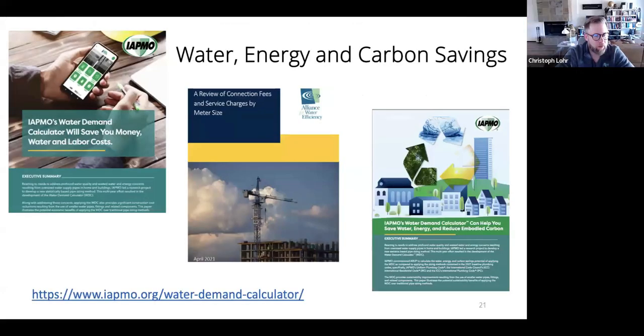Definitely. To try to quantify even more some of the potential construction, energy, and water savings, IAPMO worked with industry partners to come up with three reports. The first one, on the left, was done with Stantec consultants, which captured the material cost savings of just pipe inside buildings that utilize the water demand calculator. Three prototype buildings were selected: a single family home, a 6-unit multifamily, and a 45-unit multifamily. Working with Stantec, based on RSMeans, we found savings in the range of 5 to 15% on pipe materials in all instances. Worth noting is that this was based on pre-COVID rates for materials, so we would anticipate that some of those savings may actually increase due to the current cost of construction materials.